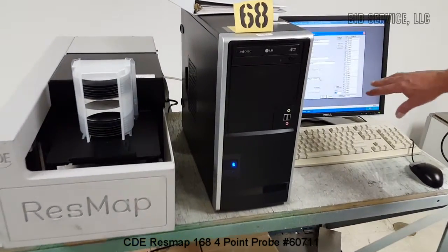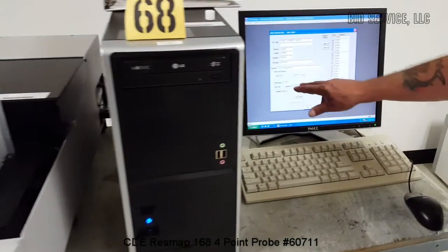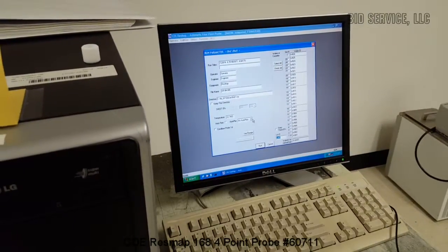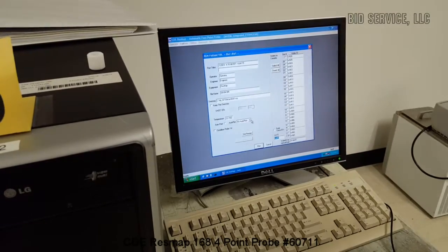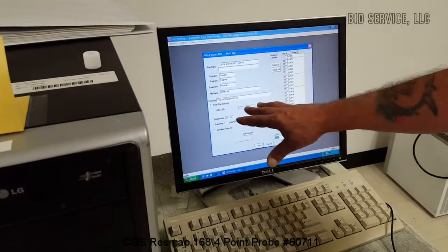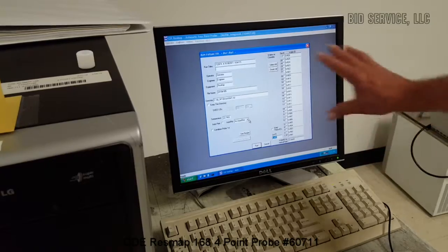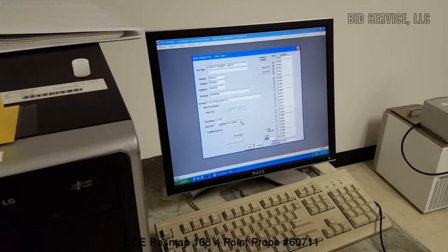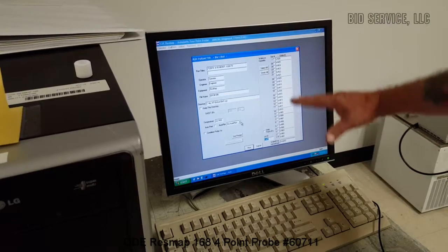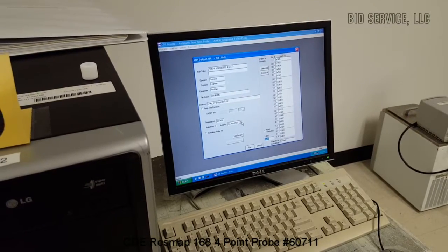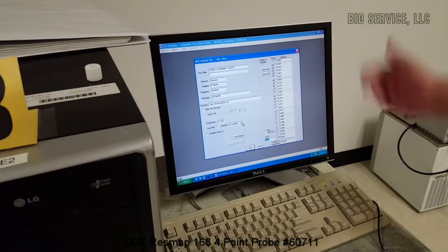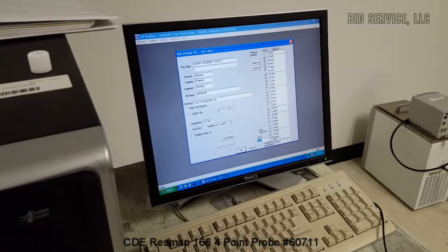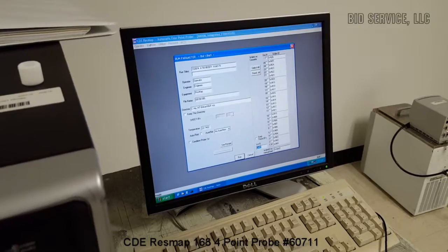And we're using the bid one recipe, which is in the bid project folder under 4MP. So you can see the directory shows up here. You can change different information according to what you need to do. And here it shows you all the positions in the cassette that you could test, and you can uncheck or check as you wish. And as you can see down here, I've got position number one checked.